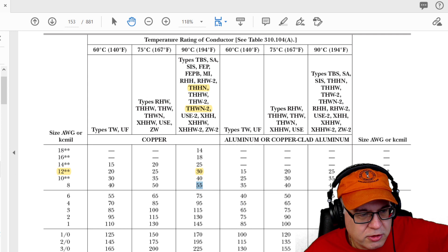Next, I need to go to 310.15(B)(2)(a) of the NEC and see what it is for 130 degrees Fahrenheit. Oh, incidentally, while I'm here, some people ask me this question, so I'll answer it. What's the difference between (B)(2)(a) with the 30 degrees C and the one with the 40 degrees C? Everything you do on an exam is going to be based on the 30 degrees, so you're going to use 310.15(B)(2)(a). But you do have other tables, like 310.19 and 310.20, that are based on 40 degrees C. Those would reference you back here. But if you're using the normal ampacities under 310.15(B)(16), things like that, you're always going to be in 310.15(B)(2)(a). You'll generally be in this one.